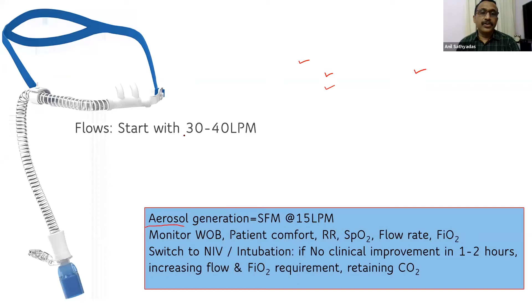For FiO2, you can increase the flow rate in the oxygen flow meter and see what is being recorded by the machine. You can increase the flow so that it reaches at least 90% to start with, and then gradually come down. Temperature, you usually have 3 settings: 31, 34, and 37. Usually start with 34 or 37, and ask the patient if it's too warm or too cold. If it's too warm, you can come down on the temperature.